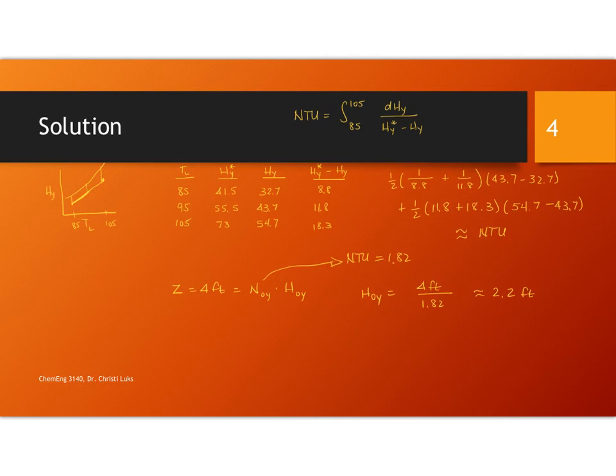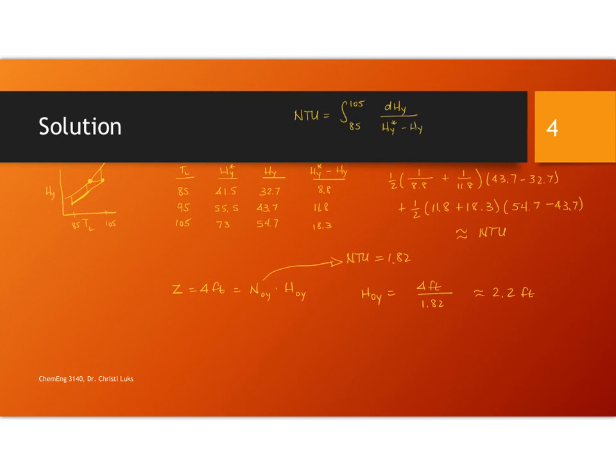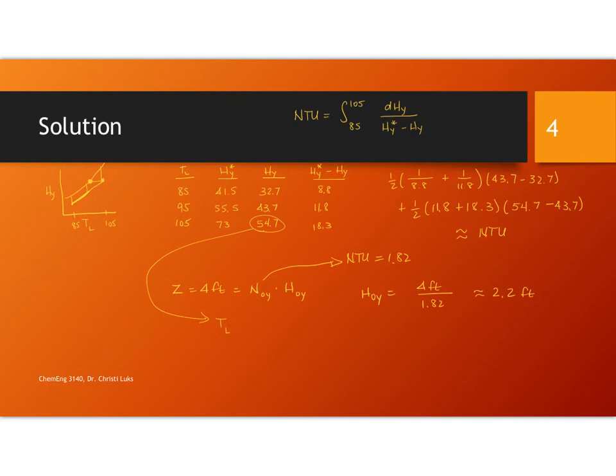If you want to know what the temperature approach is, then what you can do is simply need to look here because at the exit this temperature should be the temperature of the gas. If we're assuming it's essentially saturated, but if not, you can use this exiting enthalpy and use that to solve for T of the liquid and compare that to what you would have gotten based on the drawing. And that will tell you your approach.